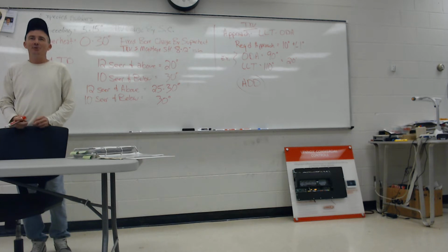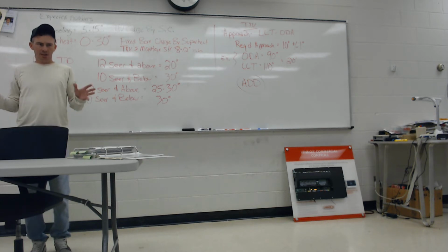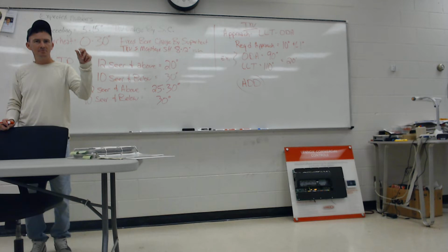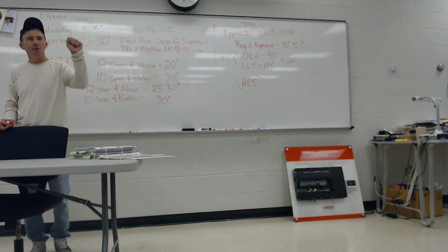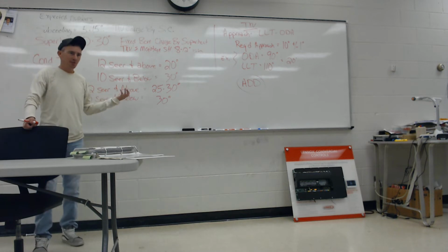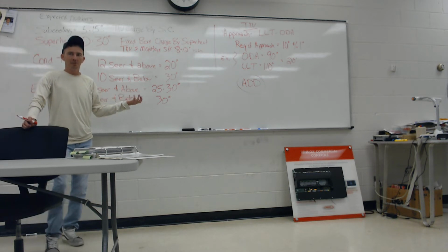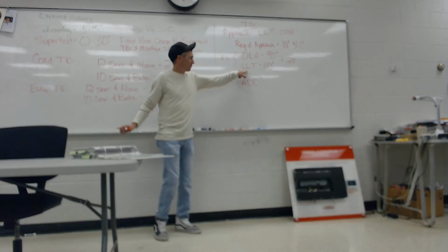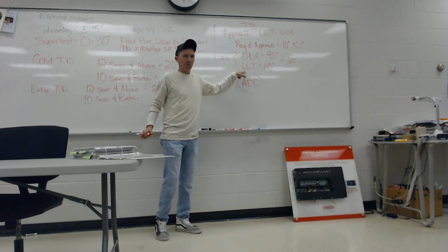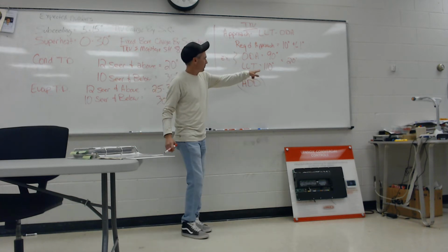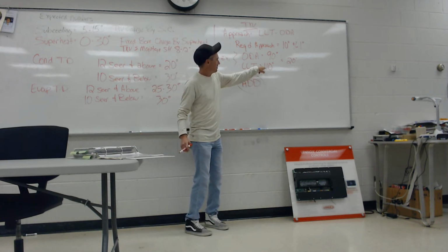It's gonna close off. You're adding more, you're flooding it more. It's gonna see the superheat start dropping, right? It's gonna start pinching off. Agreed? TXV is gonna start shutting off. When the TXV starts shutting off, it's gonna start stacking up in the condenser. If it spends more time in the condenser, what's it gonna do to our leaving liquid line temperature? Lower. It spends more time in the condenser, so we can put more of this heat into this.